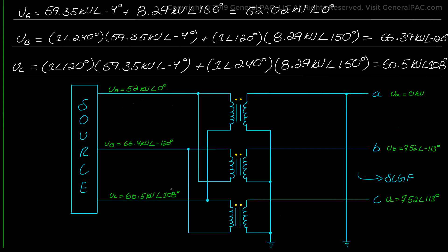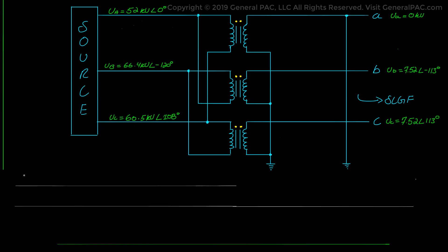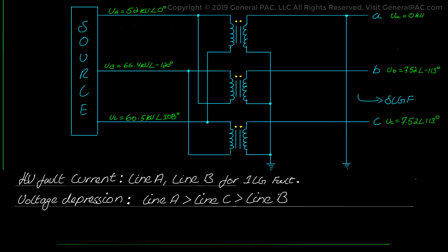For a one-line-to-ground fault, we clearly see that the high voltage line A voltage is the most depressed since the fault was on line A on the low voltage side. We will also have some depression on the high voltage line C voltage, while we don't see any significant depression on the high voltage line B voltage. This lines up very well with the current flow on the high voltage side — the high voltage fault current flows only on line A and line C for a low voltage one-line-to-ground fault on line A, due to the specific type of delta connection. In terms of voltage quantities, the largest depression occurs on line A, followed by line C, and line B sees no significant depression.